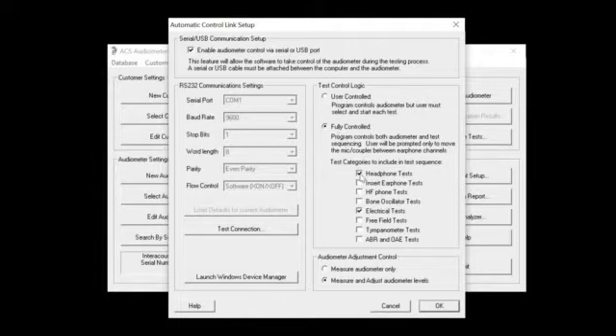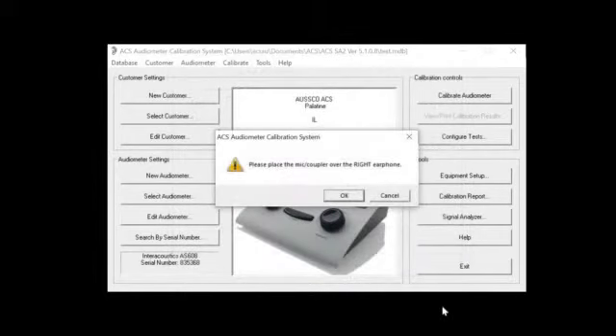Fully controlled, it knows that you're going to do the headphone test. You're not going to do inserts. You're not going to do high frequency. You're not going to do bone. But here's something. You're going to do the electrical test. Pretty tough for that to be happening if you're just using a sound level meter. We know it's not free field. We know it's not a tympanometer, and the system knows it's not ABR. We have the option of just measuring the audiometer only and doing nothing, or we can measure and adjust the audiometer levels, which is, again, the majority of time what you're going to be doing. I'll just simply click on OK and wait for some other instructions.